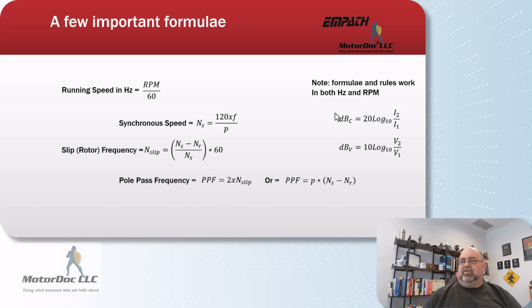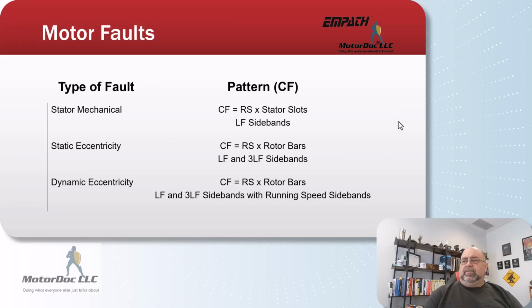This value here is the one we tend to use for both current and voltage and ESA. But in order to get the decibels, it's 20 log 10 of the current in question divided by the primary current at the line frequency, or the RMS current. Always keep it consistent. If you're doing peak, use peak. If you're doing RMS, you do RMS. Stator faults are the running speed times a stator slot. You won't see that peak. You will see the line frequency sideband.